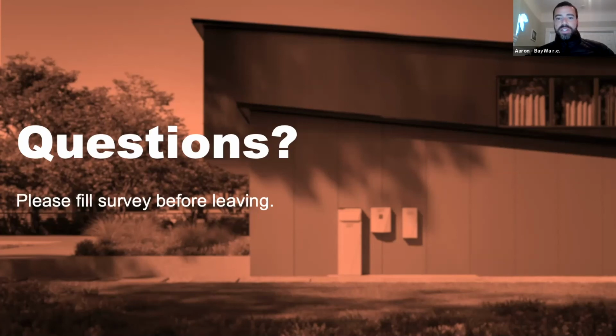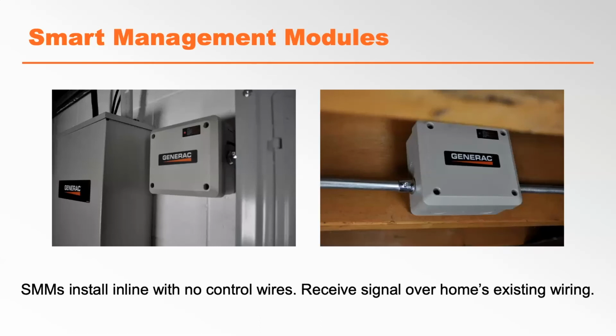Next question: how easy is it to change priorities within the SMMs? Are they set and kept the same way, or can they be changed halfway through an outage? It's pretty easy to change the priority on them. It's just a dial on the SMM if you remove the cover, and you can change it during an outage. Obviously the system will be managing those loads as you're islanded with the PWRcell system, so you want to make sure you're doing that at the right time. It's ideal to set it and leave it, but you can change it midway through.